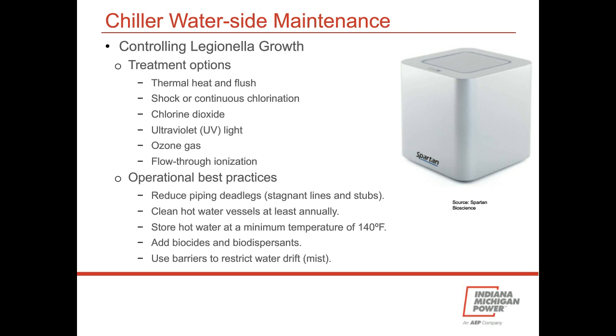And in terms of operational best practices, you don't want to keep water from stagnating in places. Temperature is important. Less than 65 degrees, more than 140 degrees is usually pretty safe. It's that in between that's a challenge. And you want to keep, this is an airborne type of a thing, put some physical barriers there, like drift eliminators or mist eliminators on the cooling towers to keep that from traveling very far. And again, I can talk a little bit more about that here at the end if you're interested in learning more about that.